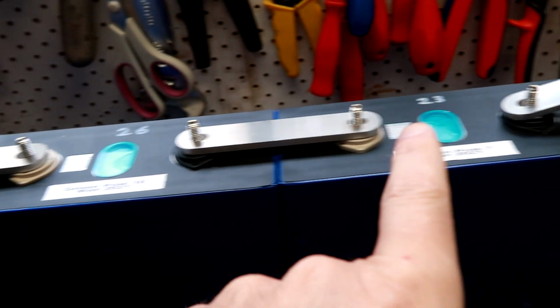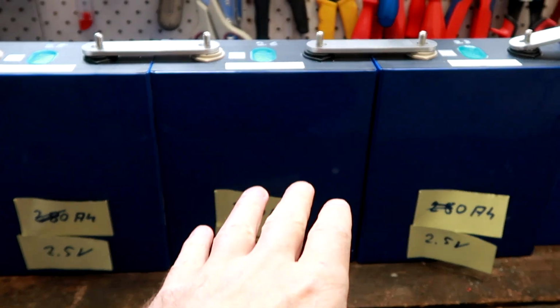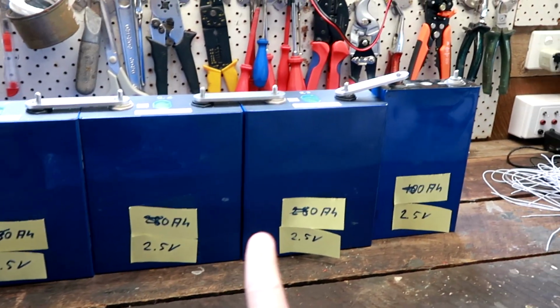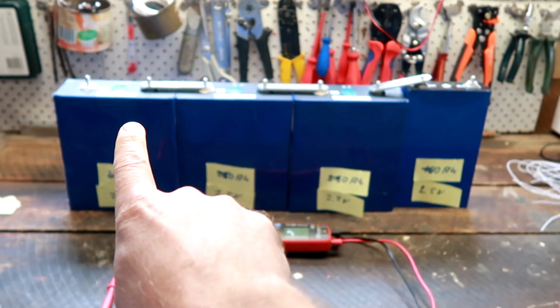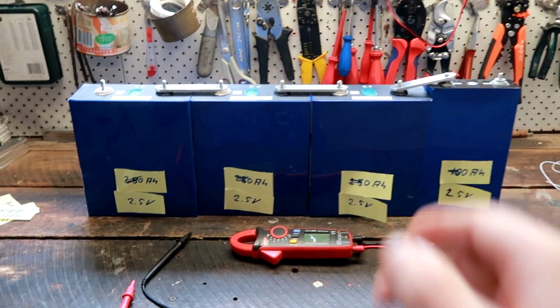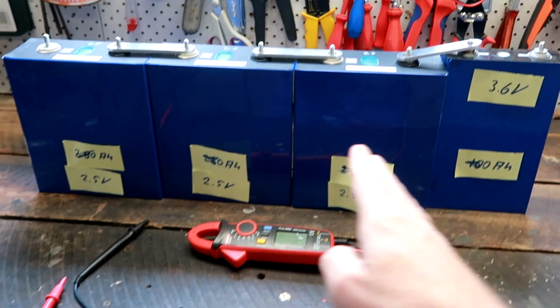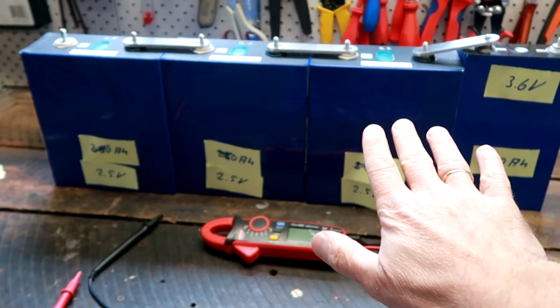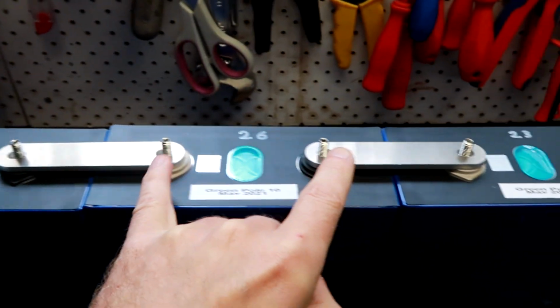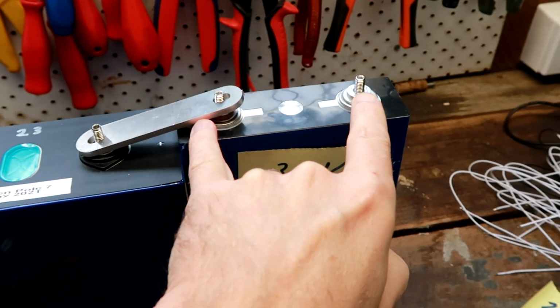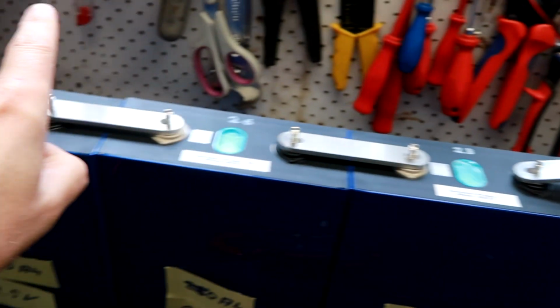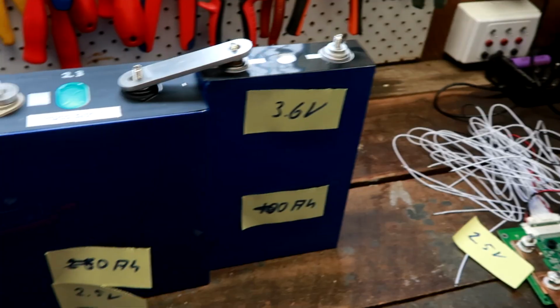And then connect them back in series and start charging up the battery. And while you are charging your battery, you take your multimeter and you measure all the individual cell voltages while charging it up. As soon as one of your cells hit a critical voltage, like 3.6 volts, you stop charging. You don't absorb, you stop charging. And then you measure the individual cell voltages of each cell, add them together, and this is your overall battery charge voltage.